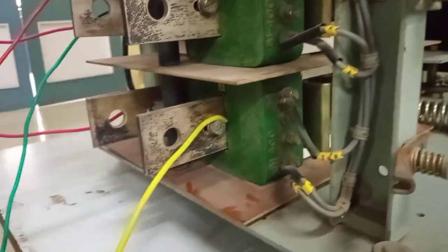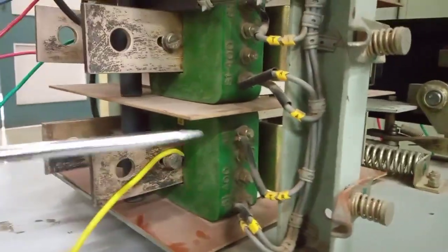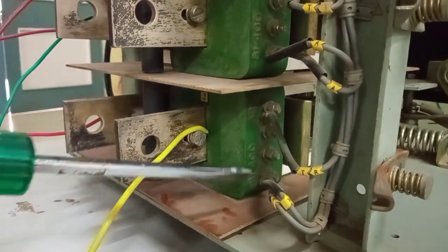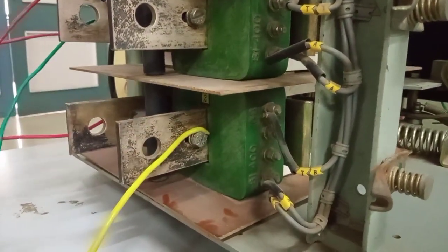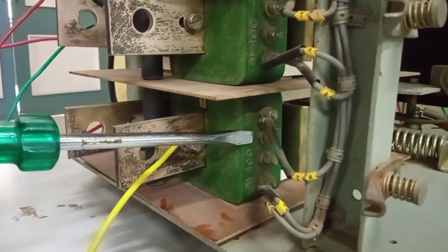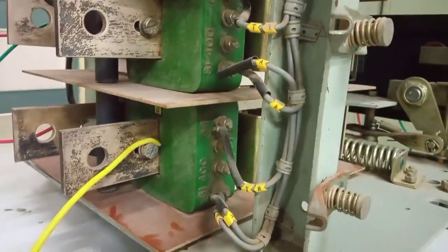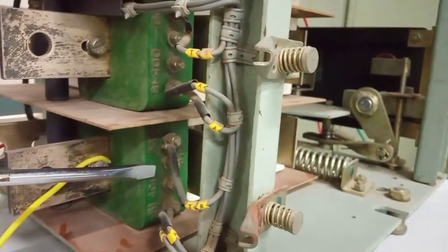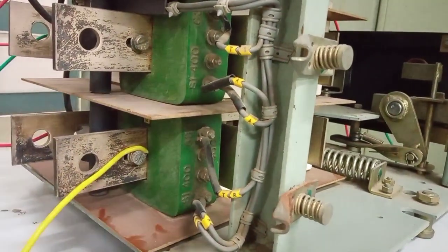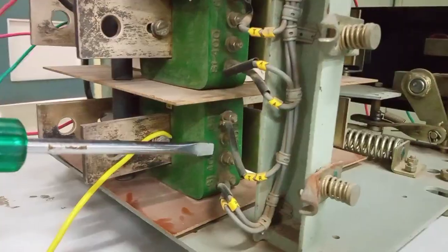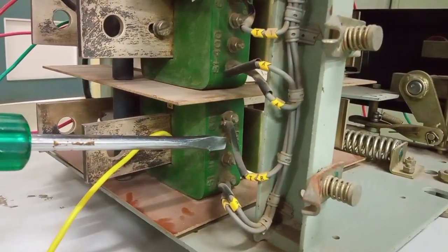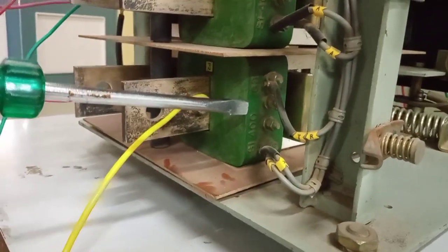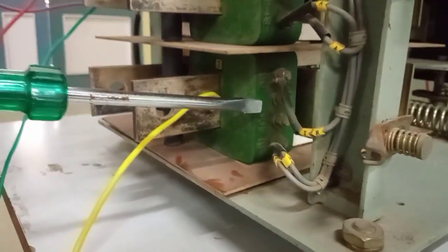Through this we will perform the overload test as well as the short circuit test, because while performing the overload test, either we have to overload from the primary side or from the secondary side. If we perform it from the primary side, the primary current is 630 ampere. So to perform the overload test, we have to pass 1.5 times, 2 times and 3 times of 630. That means approximately we require a 2 kiloampere current source, which is quite huge. It is very difficult to have such a large capacity current source.